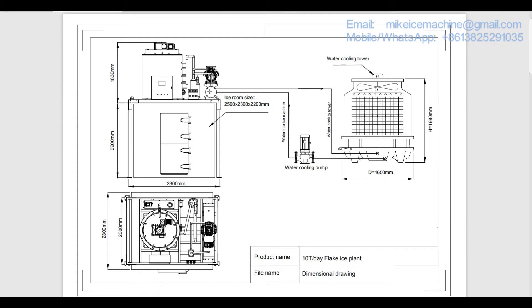This is the compressor. This is the water cooling condenser. This is the water cooling tower. This is the water cooling pump — the pump maintains the water circulation between the condenser and the cooling tower. Water goes into the condenser from this line and comes out from this line. Heat is carried from the ice machine to the tower and released into the ambient.